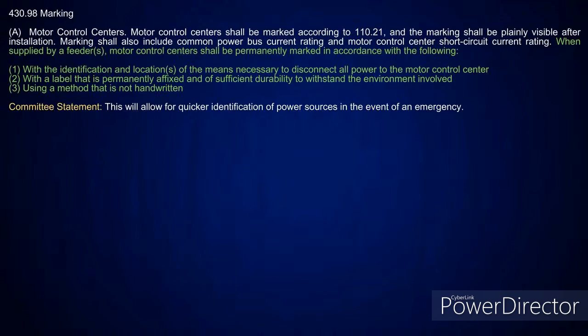Yeah. Well, this one, 430.98(A), deals with motor control centers, and what it gets into is the identification of the power sources. They still have that it's marked in accordance with 110.21. But in the event of an emergency, if you have a motor control center supplied by feeders, it tells you these motor control centers have to be permanently marked. It says, in accordance with these three items, with the identification and location of the means necessary to disconnect all power to the motor control center, and with a label that is permanently fixed and of sufficient durability to withstand the environment involved, and that it's not handwritten. So basically there has to be something telling the location of the disconnect for that motor control center in case of an emergency.